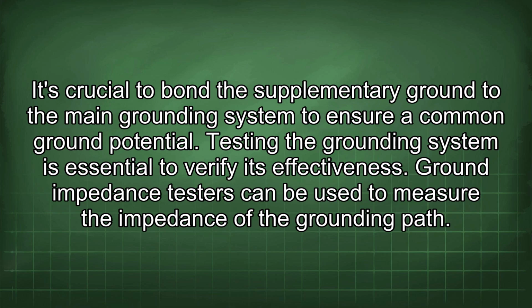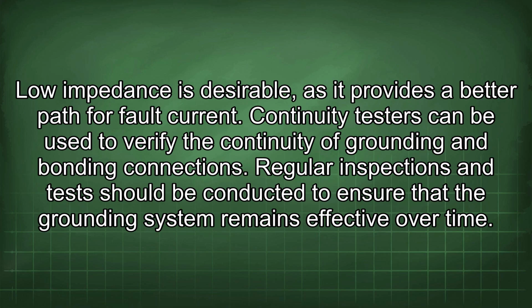Ground impedance testers can be used to measure the impedance of the grounding path. Low impedance is desirable as it provides a better path for fault current. Continuity testers can be used to verify the continuity of grounding and bonding connections. Regular inspections and tests should be conducted to ensure that the grounding system remains effective over time.